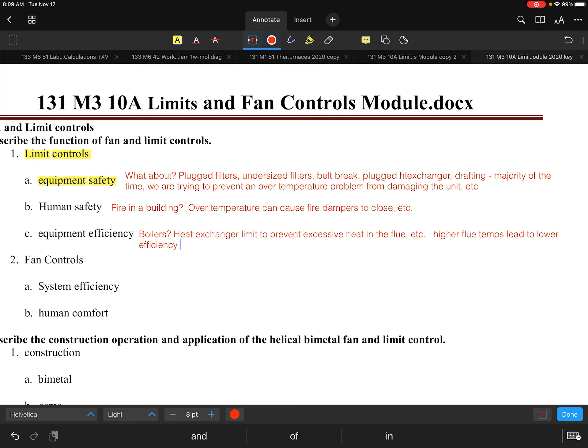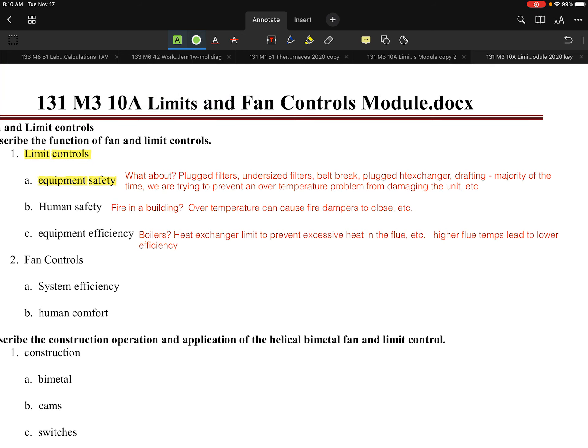A simple example: if you took two air systems and one is moving 200 CFM more than the other, the system moving more air would have better efficiency — it pulls more heat out of the heat exchanger, yielding a lower flue temperature, which means better efficiency overall.